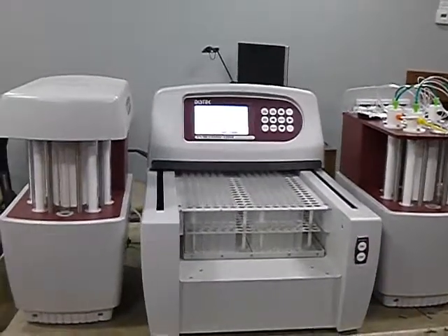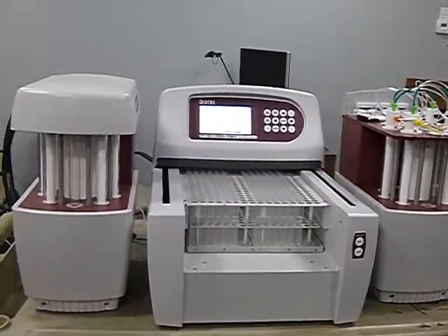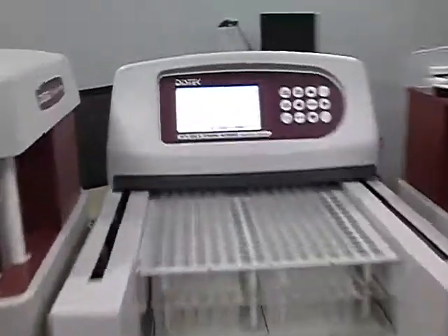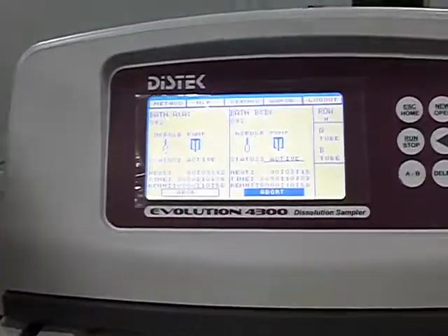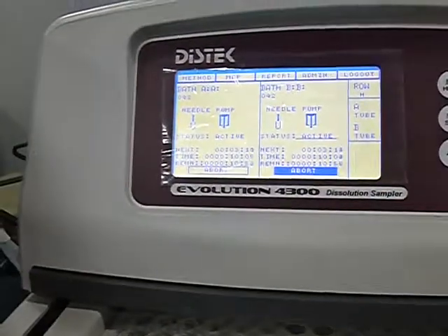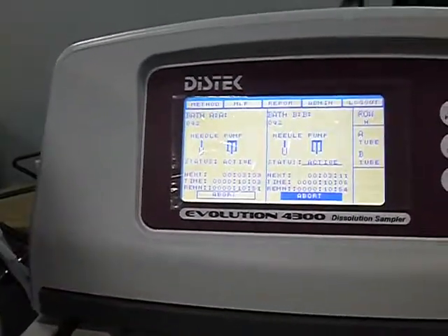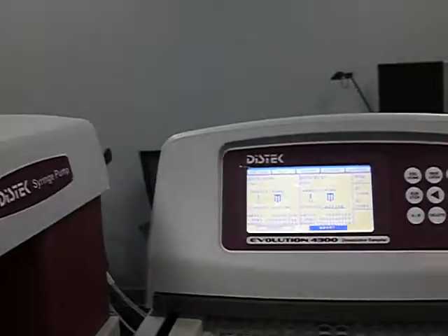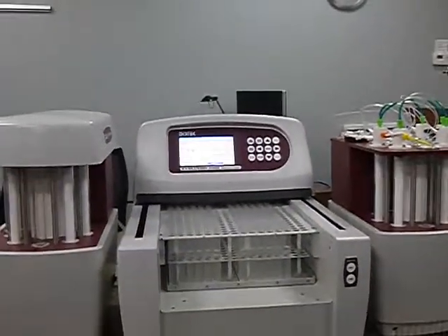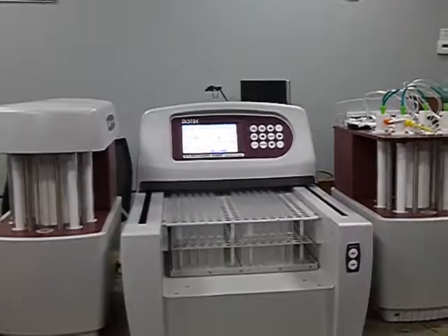Yeah, you will have your initial mass when you weigh. I do the pH adjustment separately, side A and side B, I do it separately. We mean that for OQ1, OQ2, and OQ3, you always have to have the beakers either filled up with some quantity of water, or empty.